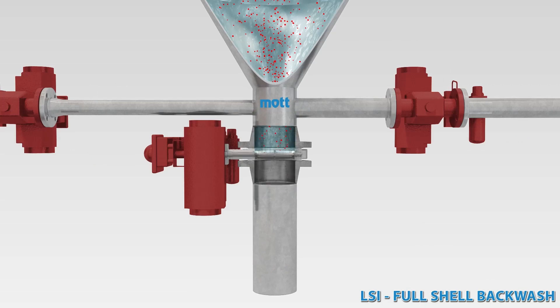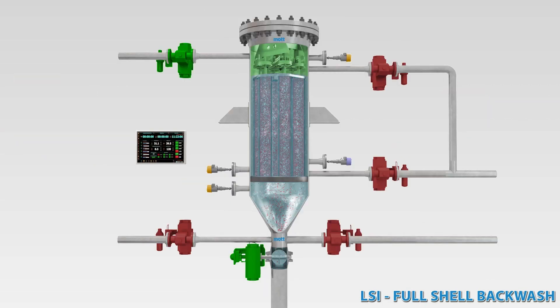The solids discharge valve is actuated. The expanding gas pocket forces liquid in the reverse direction out of the vessel, removing solids from the porous metal media's inner surface and flushing a concentrated slurry out of the filter vessel.